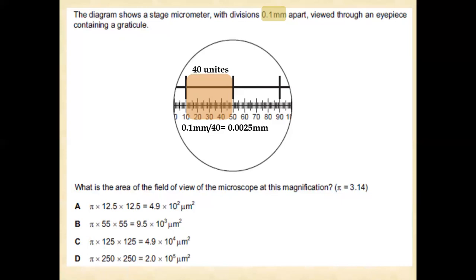So now we will multiply this unit by 1,000, because 1 millimeter contains 1,000 micrometers. So that is 0.0025 multiplied by 1,000, answer is 2.5 micrometer. Now the smallest unit of eyepiece reticule, or the smallest unit of the eyepiece reticule scale, is 2.5 micrometer.